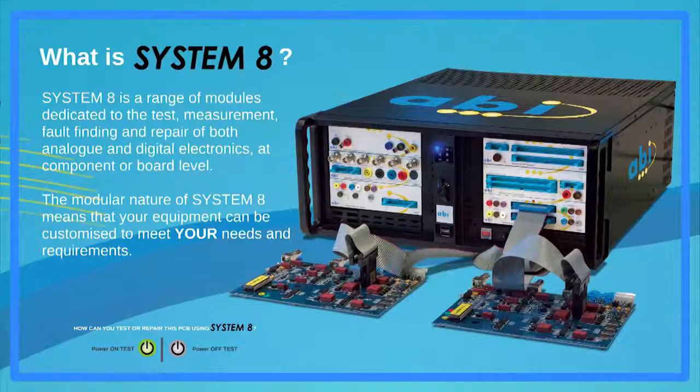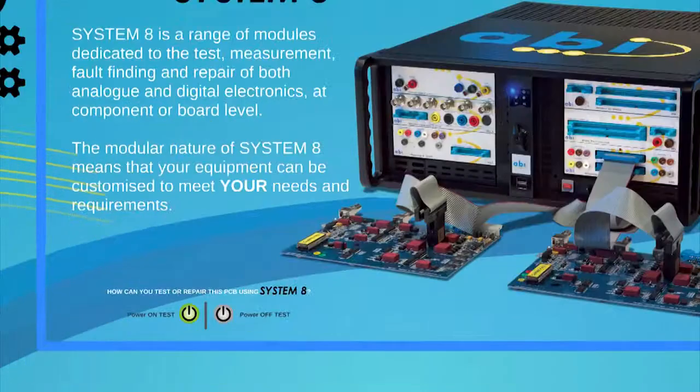The System 8 automated software controls all the modules and their tools that can be used as a standalone or as part of an interactive test sequence called the test flow. The test flow manager will allow you to save test results as well as instrument setup, pictures, videos and test instructions in a computer file that can be shared or stored for future reference. At the end of a test, a comprehensive report is generated providing detailed information about any fault found during the test.